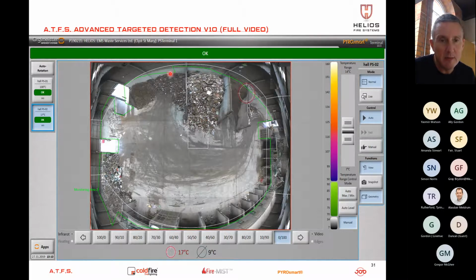So you will see here we have the screen made up of 1, 2, 3, 4, 5 scans. So that screen is made up of 5 or 6 bands, and inside those bands are the image and the temperatures for those images. So again, going back to what we said before, we have our hotspot. This is our new trigger point, which is 17 degrees. But also now we're able to tell the ambient temperature inside that building, so we don't get false alarms based on temperature drop.